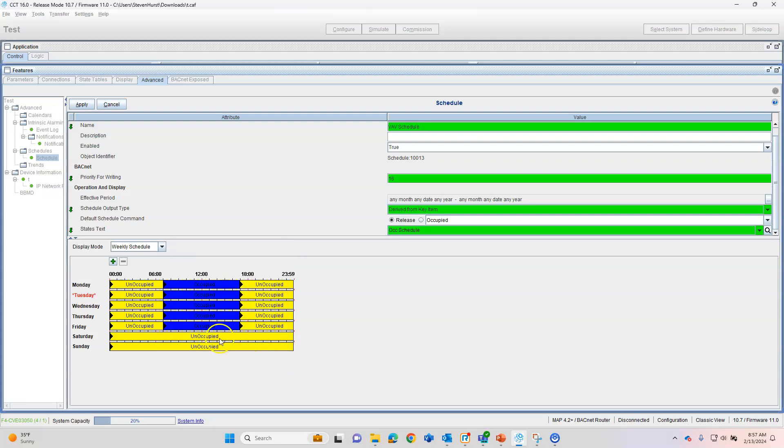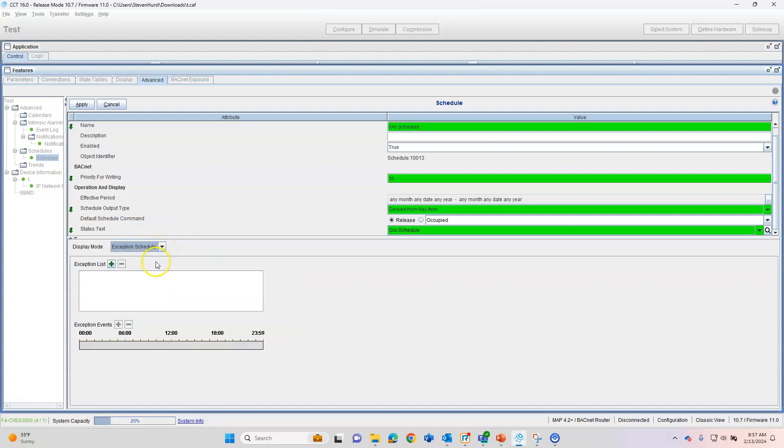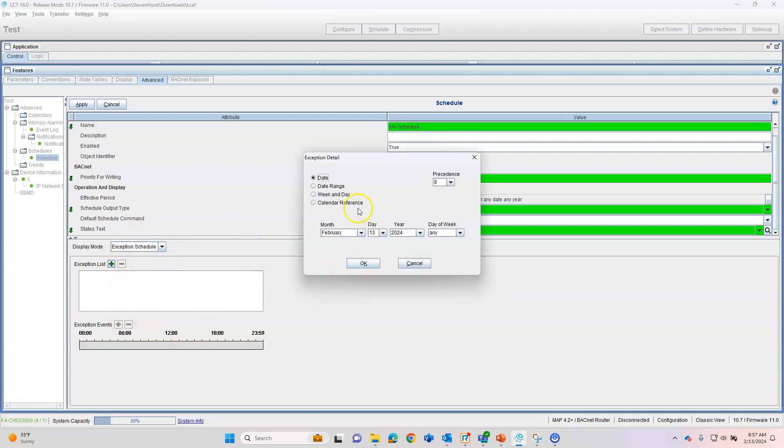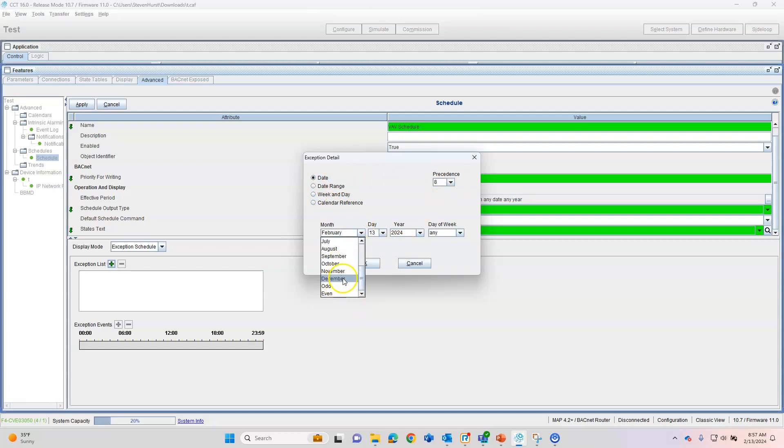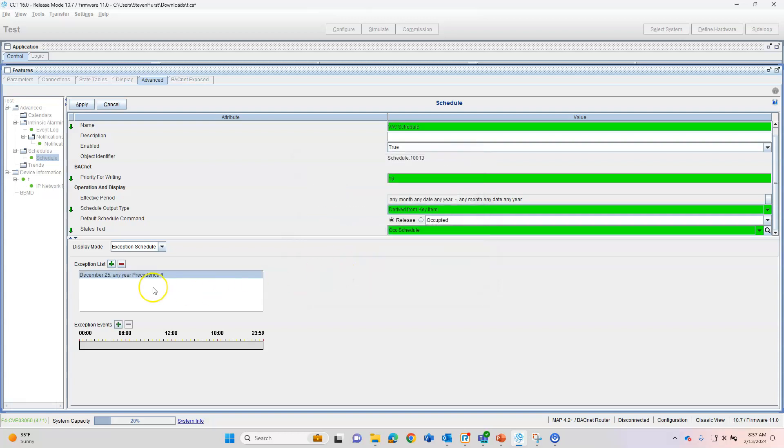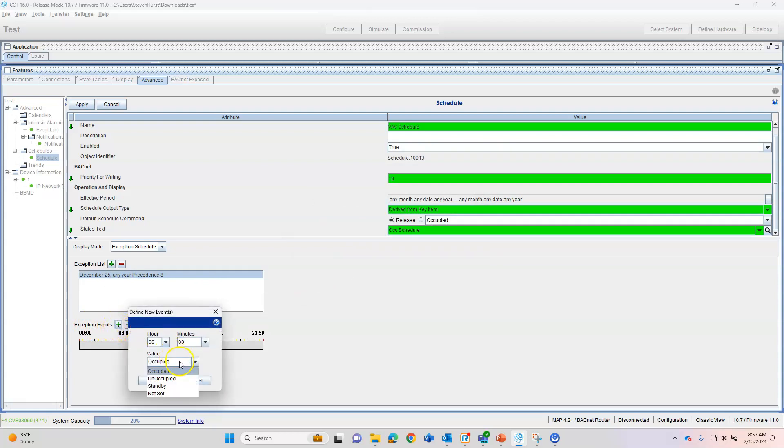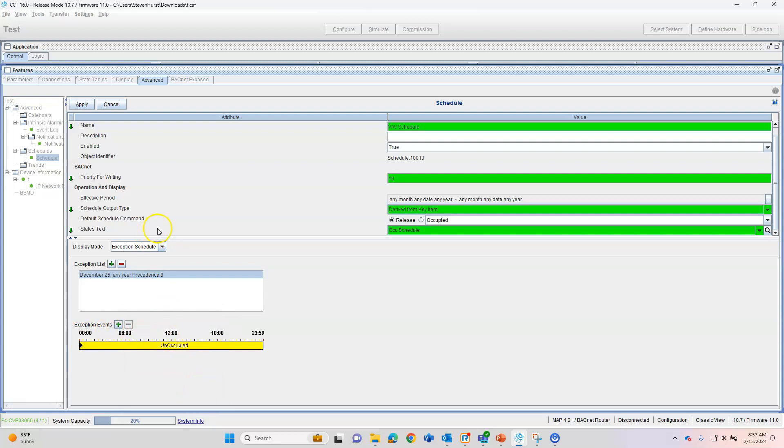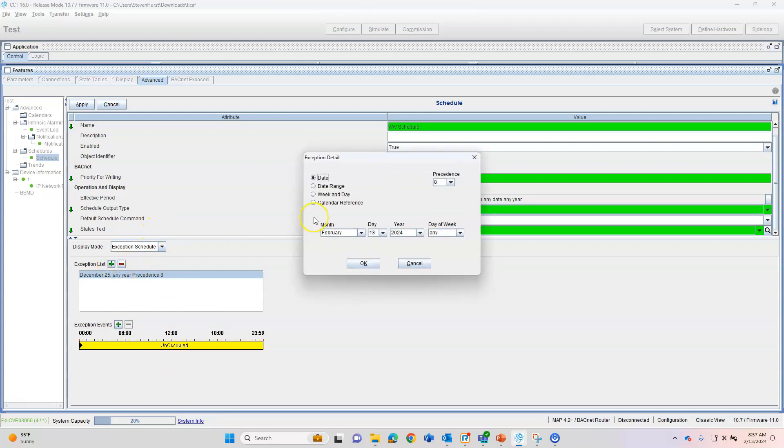Now we have our schedule built. We can also add exception dates to this, any kind of exceptions that we want through an exception schedule. We can choose some days, date ranges, day of the week. So we'll start with a date. We obviously know some dates here. We can do December 25th. Here in North America, a lot of retail stuff closed that day, a lot of offices. Any day of the week, we add that in. We also have to do our exception events. Don't forget that. So we want it unoccupied all day. Done.